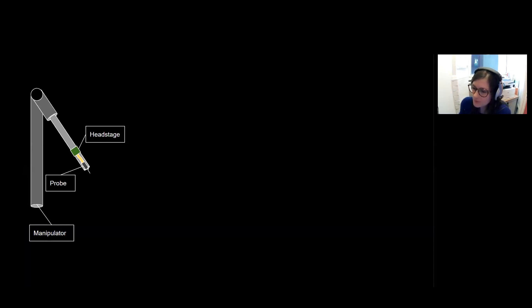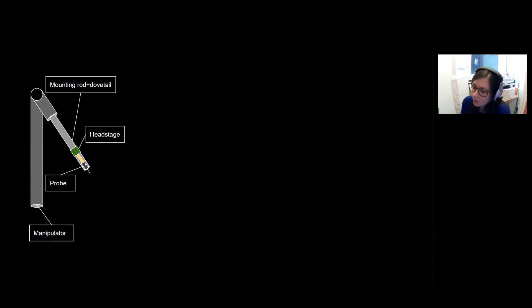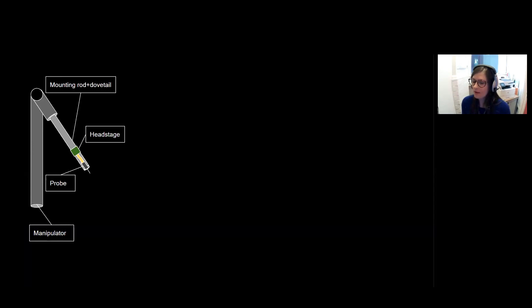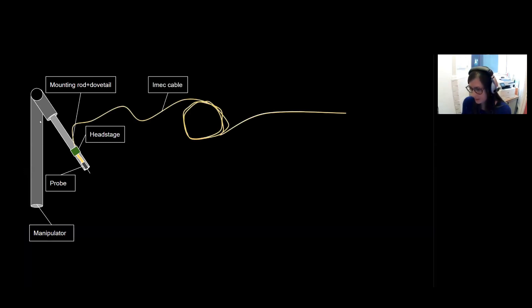So typically you would have some manipulator on which a probe would be affixed, which is connected to a headstage. For 1.0 probes, you need one headstage per probe. And for 2.0, you can record up to two probes with the same headstage. And this probe is then mounted onto some sort of rod. Some probes come already with dovetails pre-mounted on the probe base, which makes it easy to mount these probes on a rod. And others come without that and you have to manually do this.